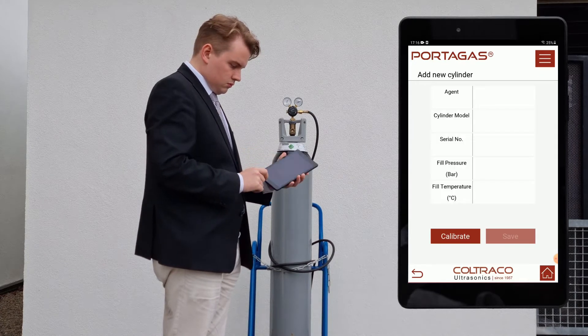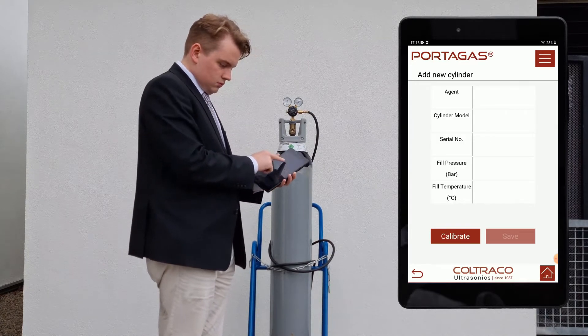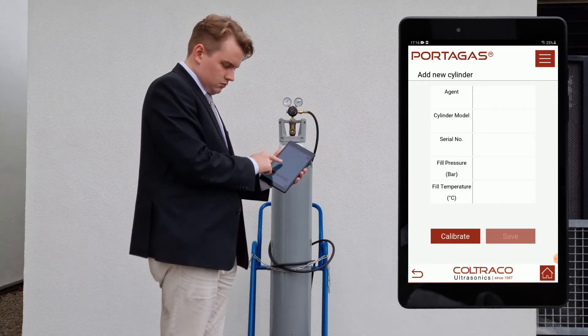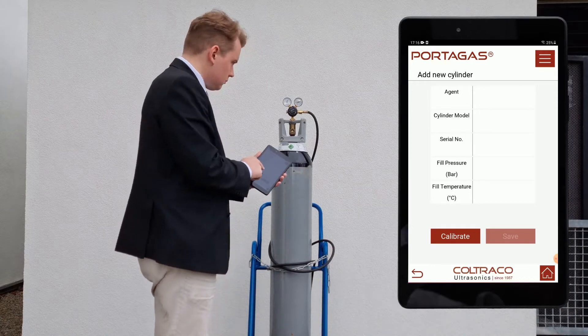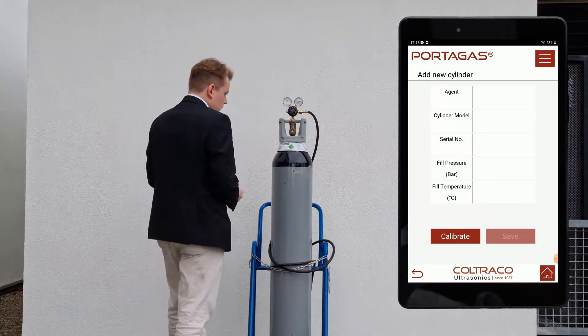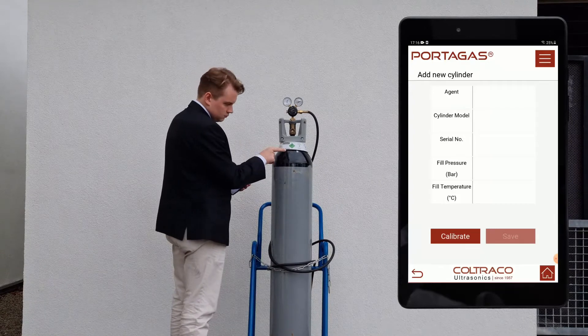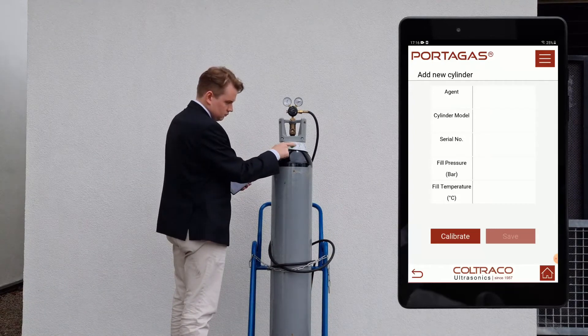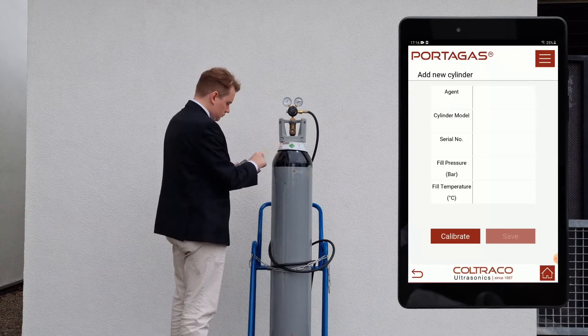Angus then adds a new cylinder and enters in the required cylinder information, including the agent, the cylinder model, the serial number, the fill pressure, and the fill temperature.